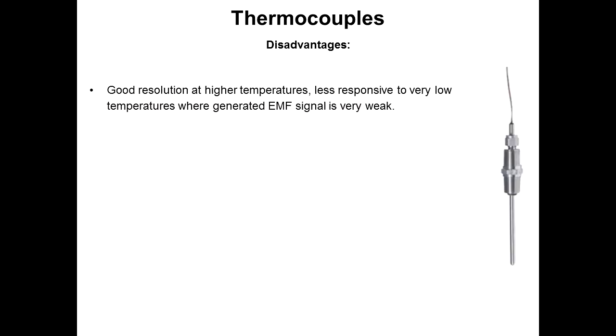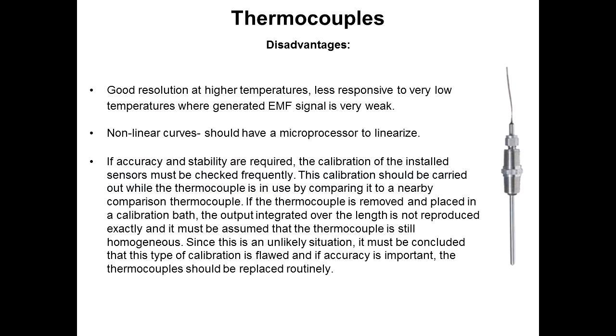Good resolution at higher temperatures, very bad resolution, or very unresponsive, at very low temperatures where the signal's weak. Nonlinear curves, so ideally you should have a microprocessor to straighten them out for best accuracy. If accuracy and stability are required, the calibration of the installed sensors must be checked frequently, especially if you're getting a lot of temperature cycles and you're running up to high temperatures. That will make them change much more rapidly. Also, because there can be corrosion along the length of the probe, either the wire inside the probe or the transmission wire, they ideally should be checked in place.